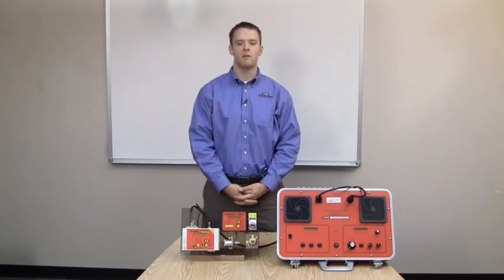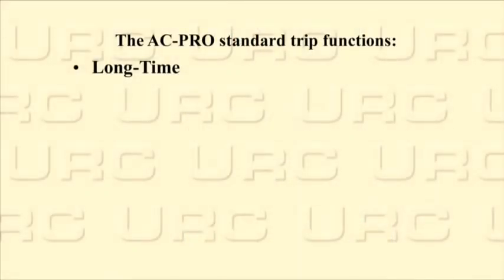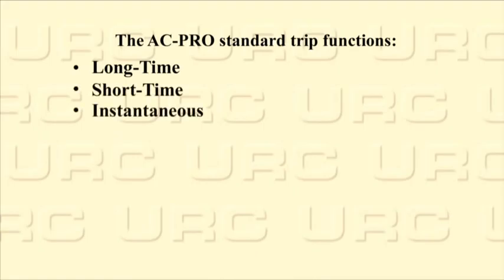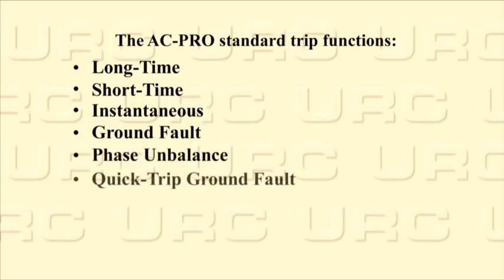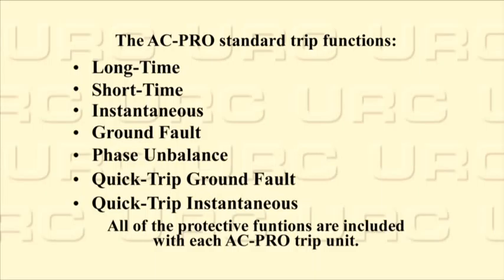Each AC Pro has the following standard trip functions: long time, short time, instantaneous, ground fault, phase unbalance, quick trip ground fault, and quick trip instantaneous. All of the protective functions are included with each AC Pro trip unit. The AC Pro has been designed to make selective coordination easy. The AC Pro has an intuitive programming interface with settings made in amps and seconds, not percentages and unrelated time band labels. Every setting is selectable off, except for long time and quick trip instantaneous.